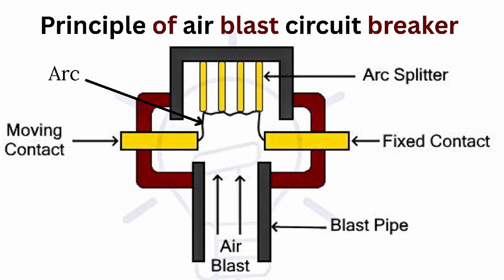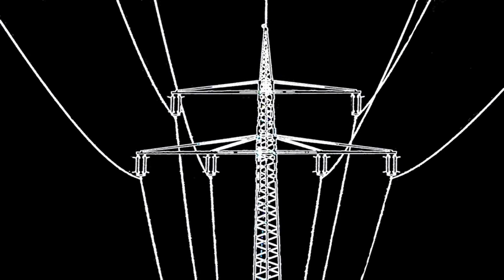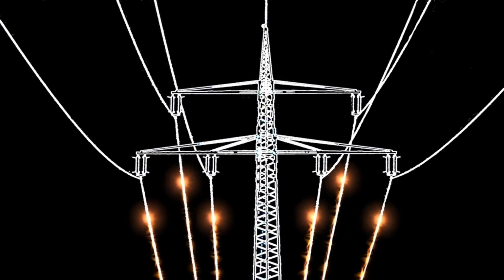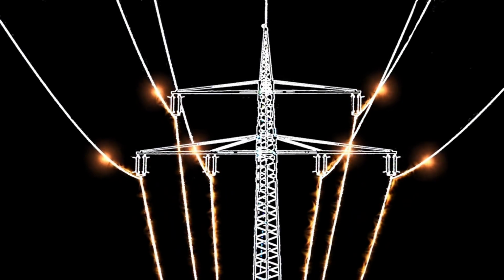As the arc develops, the high-pressure air blast is released, which rapidly cools the arc, reducing its temperature and ionization. The air blast also blows away the ionized particles, increasing the dielectric strength of the gap. As the arc is cooled and the ionized particles are removed, the arc resistance increases, ultimately leading to arc extinction. The air blast circuit breaker's design ensures that the arc is extinguished quickly and efficiently, minimizing the risk of damage to electrical equipment. So, this is how an ABCB clears a fault in the power system and protects electrical equipment.